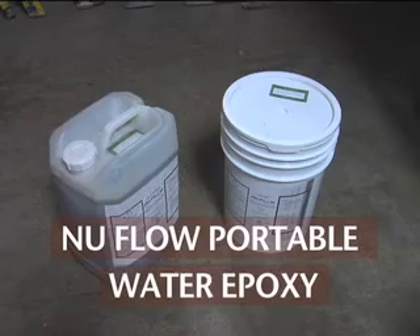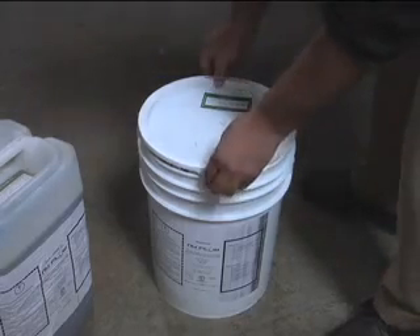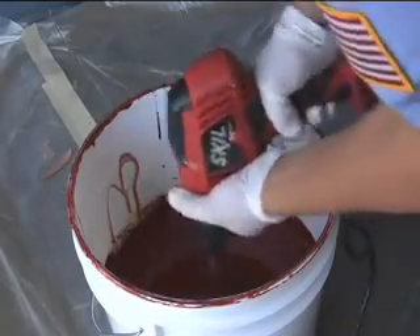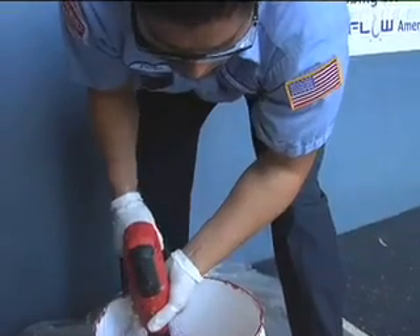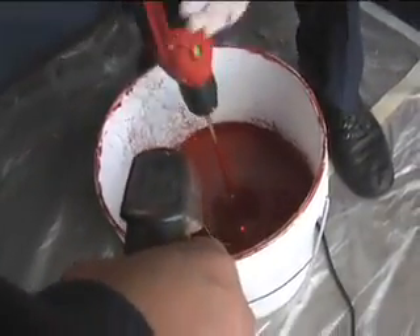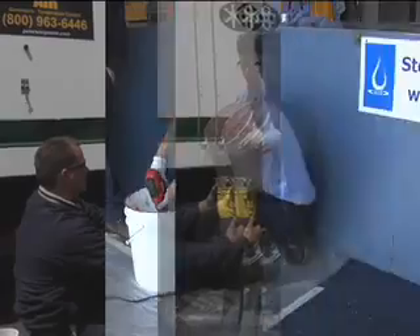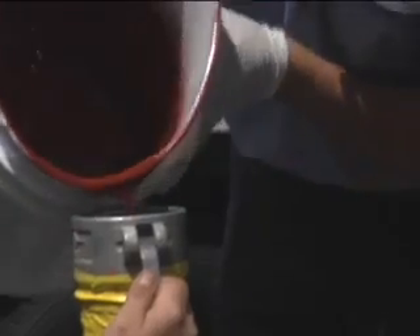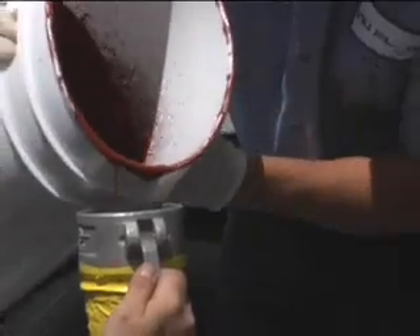The Nu Flow potable water epoxy is a two-part epoxy. Once the resin and catalyst are combined, Nu Flow mixes the epoxy using a drill and paddle based on ambient temperatures. Today we will be mixing the epoxy at 90 degrees Fahrenheit.